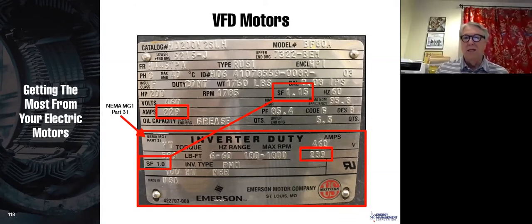And in this case, the manufacturer says the full load amps without a VFD is 229, and the full load amps with a VFD is 239. So what that's saying is that this motor is conservatively designed enough such that they can give you a little bit of your service factor back. They're going to take most of that 1.15 service factor, but they're going to give you just a little bit back and actually allow you to run at 239 amps at full load on a variable frequency drive.